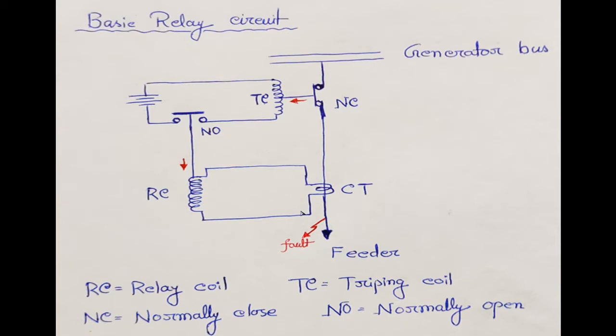During the normal operating condition, when there is no fault, normal current is flowing in the feeder, and the CT secondary is always energized. The CT secondary also carries some current, but this current is not able to produce enough electromagnetic force to move the plunger in the downward direction. As the plunger does not move downward, this normally open switch remains open during normal operating condition, so the tripping coil is not energized, and current is not able to flow from the battery to the tripping coil. So that means this normally closed switch remains closed.